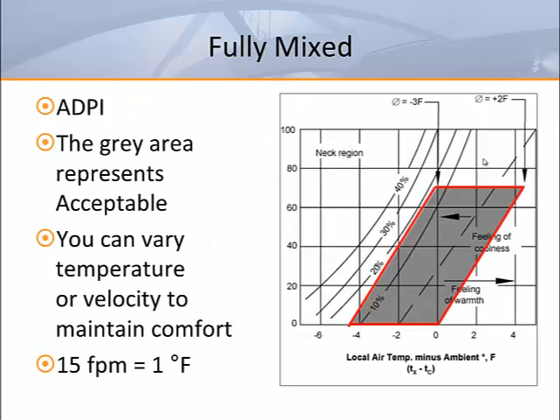For fully mixed air systems, Air Distribution Performance Index, also known as ADPI, was developed by ASHRAE in the 1960s to relate temperatures and velocities in the occupied zone to occupant satisfaction. Temperature and velocities taken in the occupied zone are used to calculate the effective draft temperature points and plotted on the chart shown. The number of points inside the parallelogram divided by the number of total points tested determines the ADPI.